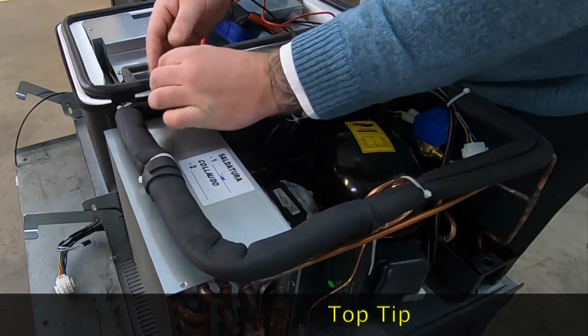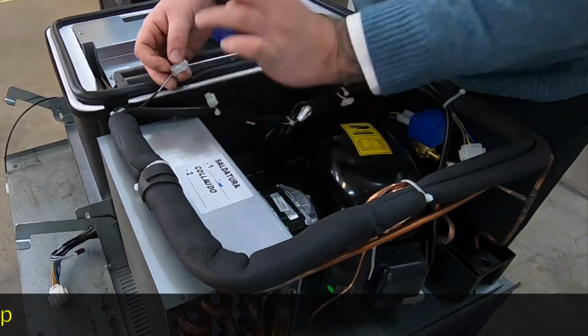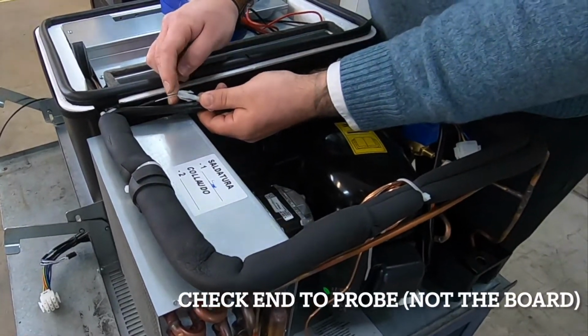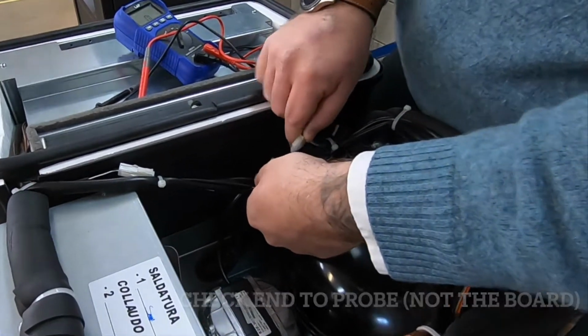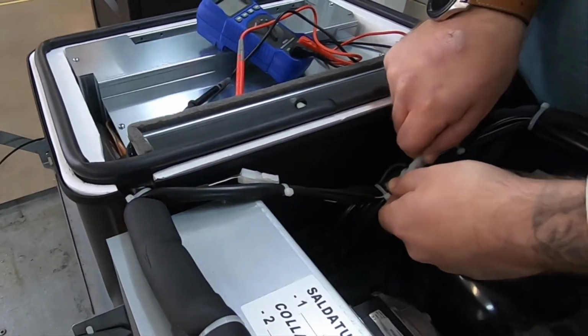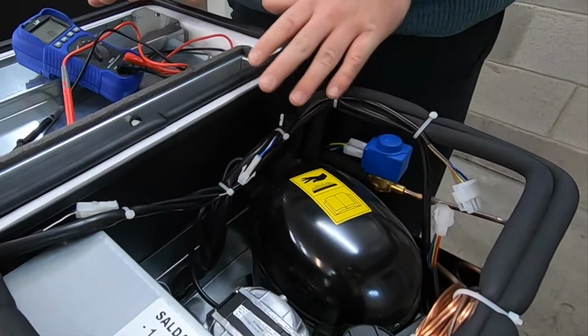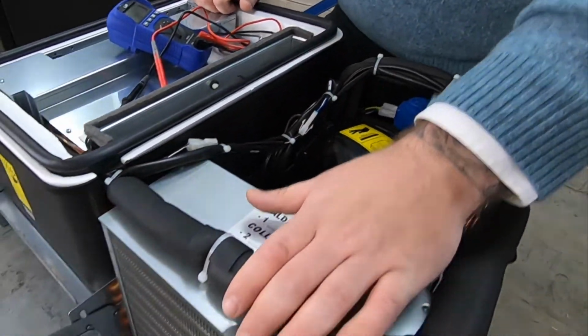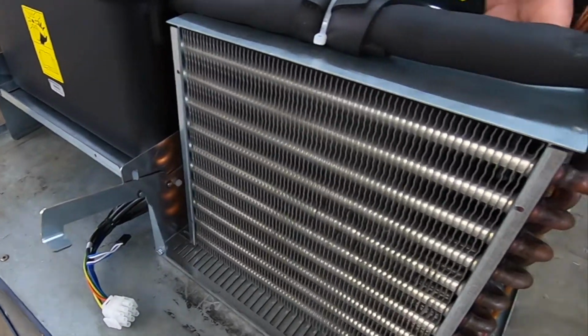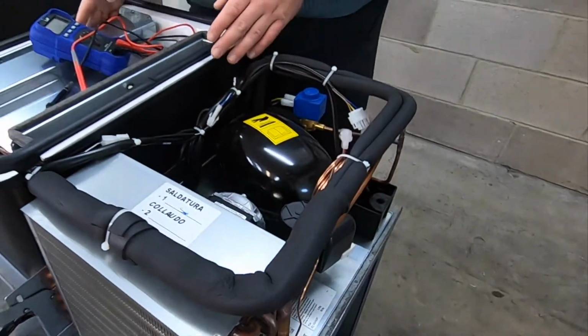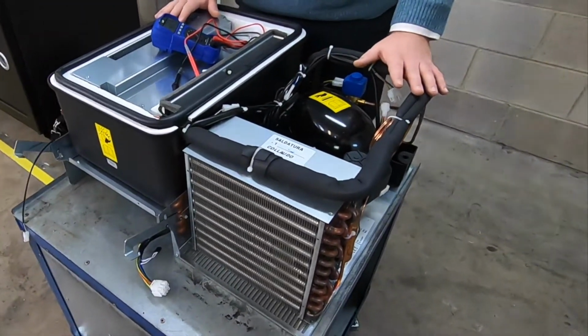Obviously just check you're testing to the end of the probe and not back to the board - just a little tip, because I'm sure we've all done that at some point. Once we've done that, we know our probes are okay, we've cleaned the front of our fridge so that's had a health check, and we've checked our fans are running. Happy this fridge is all working - put it back in the machine.